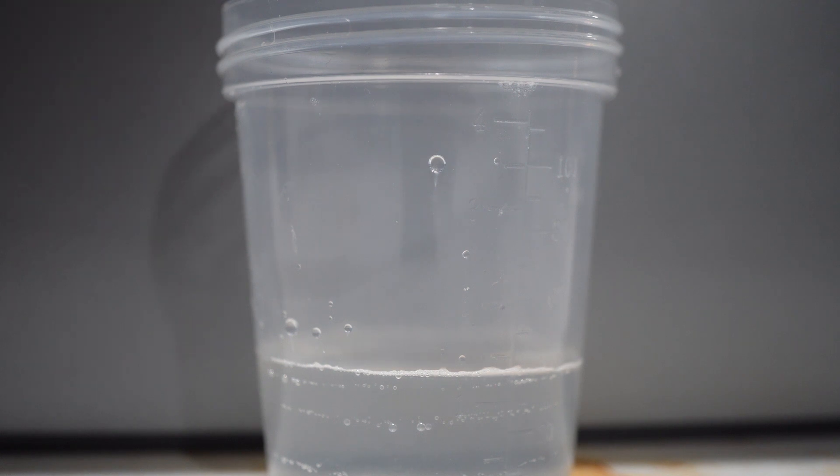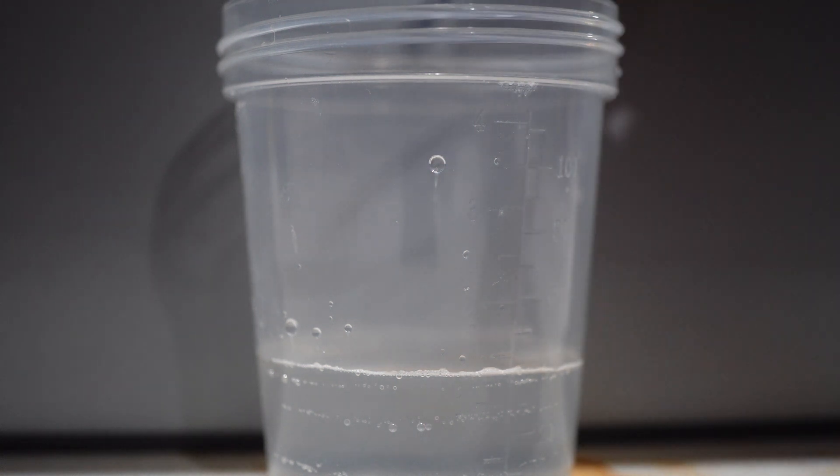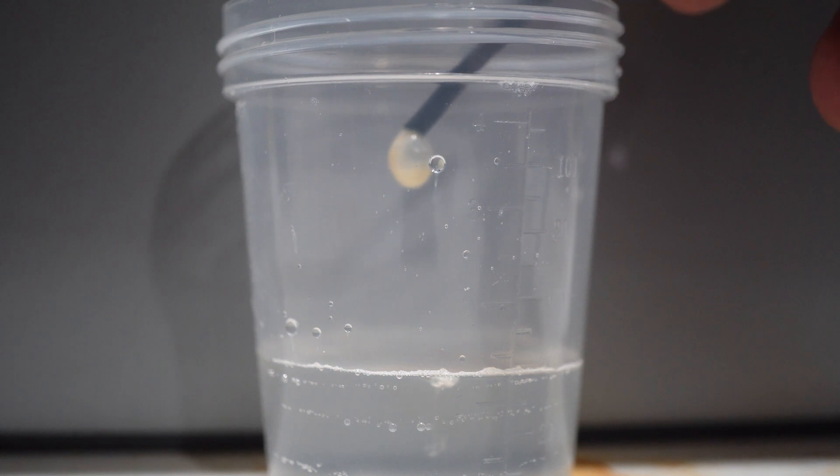So it's very important to purge your lines and not delay in replacing your reagents so that your testing can continue and the flow of water can continue. Occasionally you may want to run your fingers over the feed line, feeling for any bumps or lumps in the black line, especially near the connectors, to ensure that there are no obstructions in that line. You can put some water in your mouth and try to blow water through that line to make sure that it comes out really quickly on the other side.